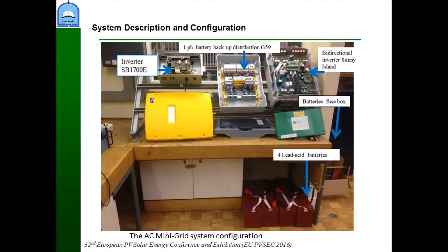It can be integrated with another source of energy, such as a PV inverter, as you see in my slide. From the PV inverter, we can connect the local load as well. If we need to integrate it with the utility grid, we can, but we need to provide a switching box to protect the network from injected high harmonics, disturbance, or any external effect that might cause a problem for the distribution network.